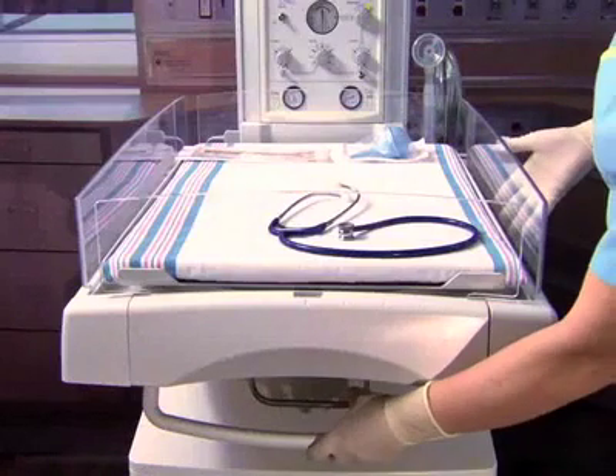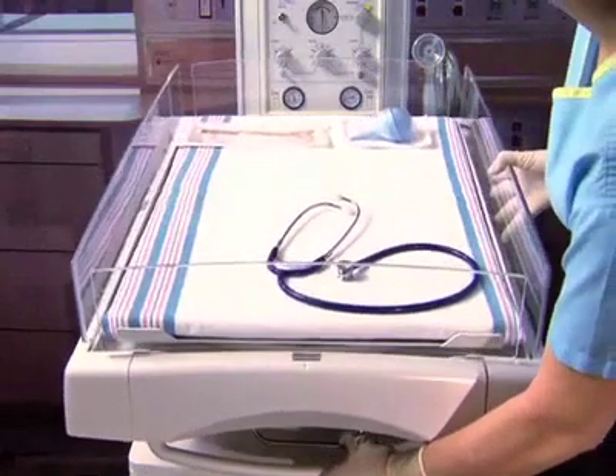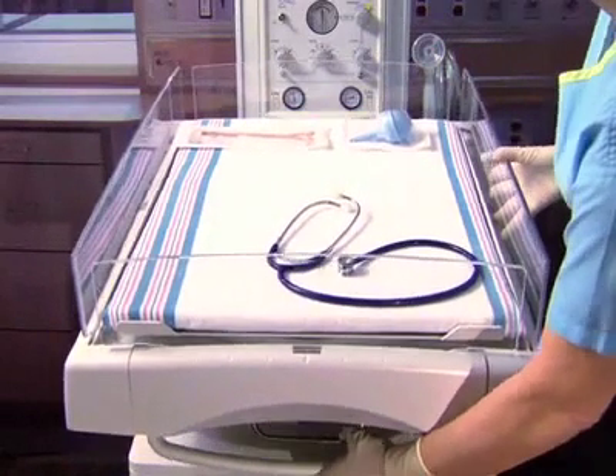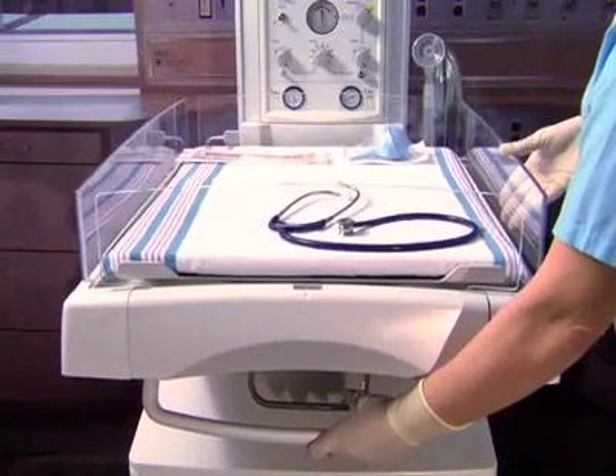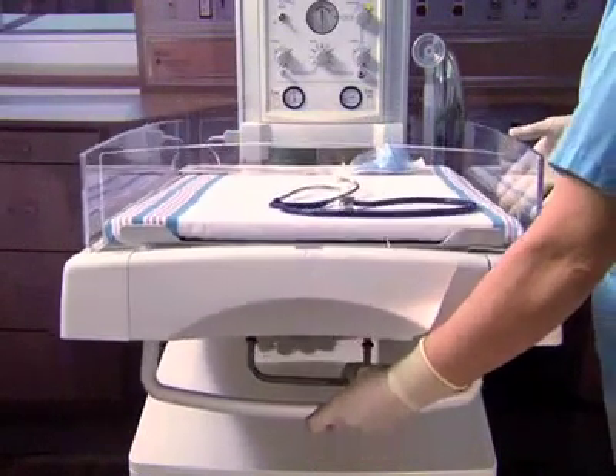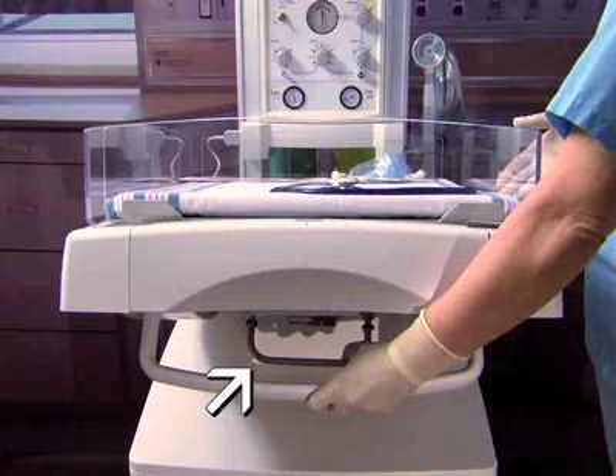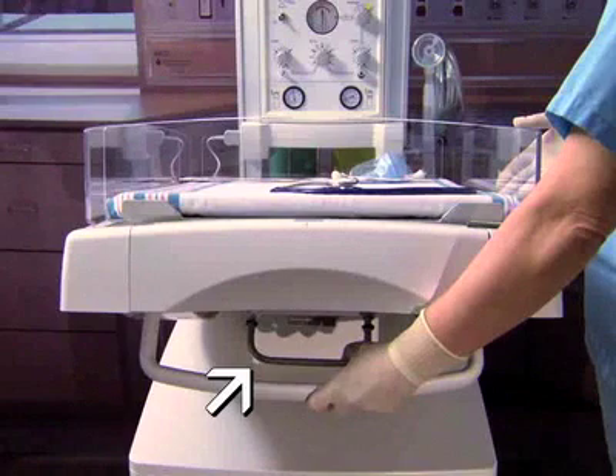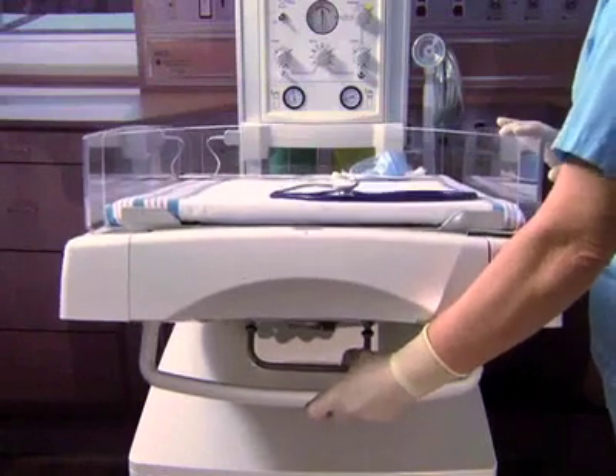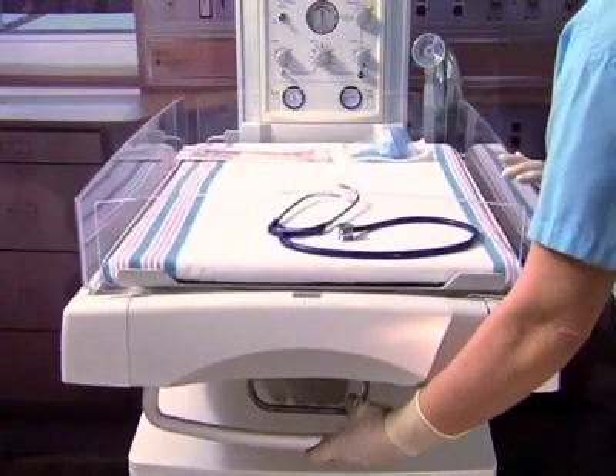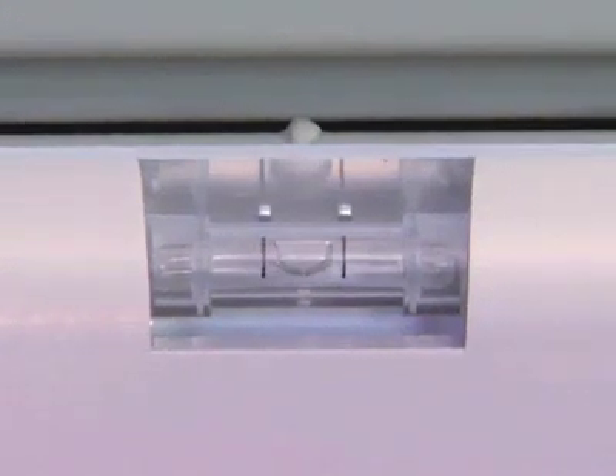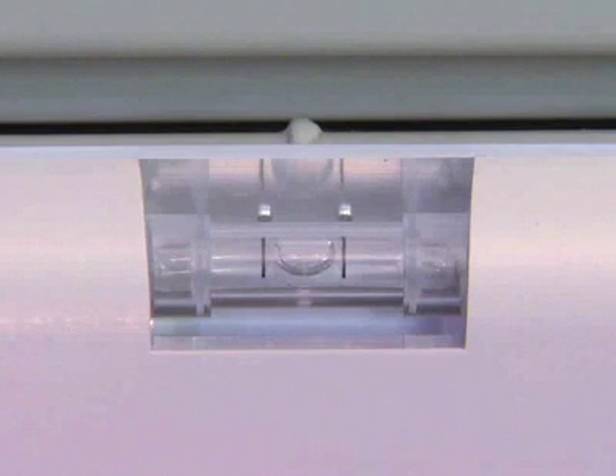The bed tilt handle lets you gently position the infant for treatment. It tilts forward and backward plus or minus 12 degrees. The recessed handle location protects against accidental bed movement. To return the bed to a level position, for example, to weigh the baby or perform an X-ray, a side level indicator located on either side panel lets you know that the bed is level.